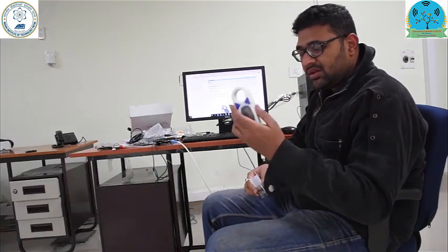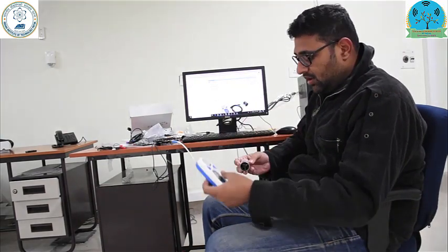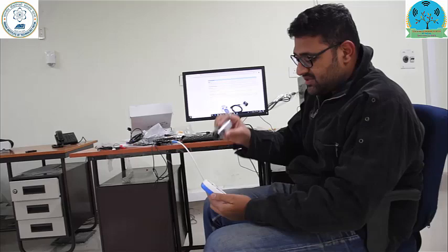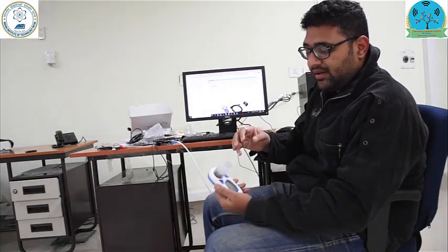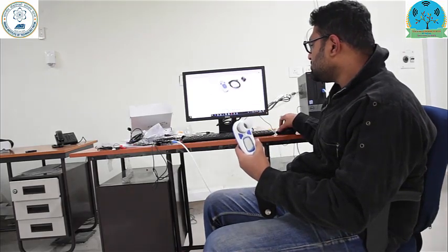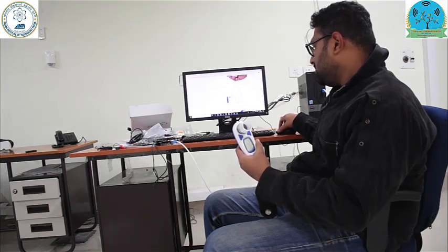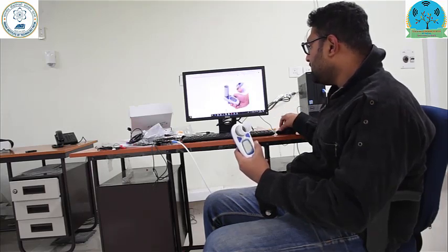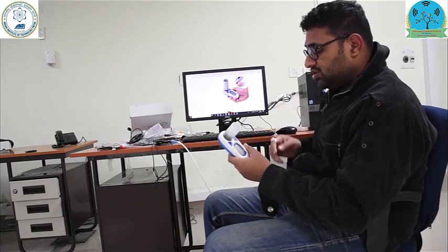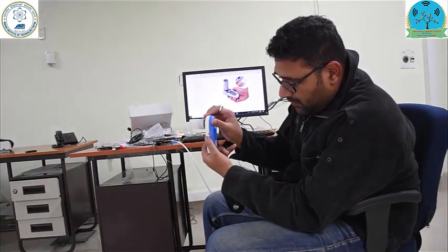So just to demonstrate it to you, this is how a spirometer looks. You can have a look at this, and we deploy the sensor in it, where we have to flow the air in this tube, as you can see in the image also, and it will measure the amount of air flowing per minute.